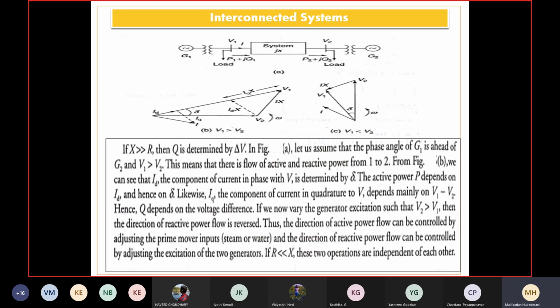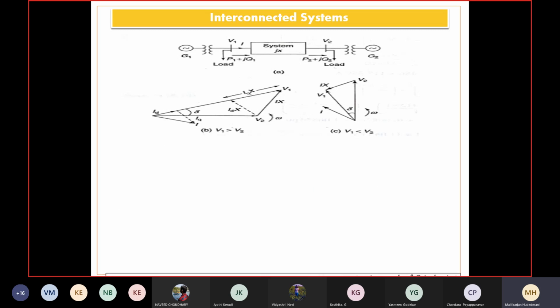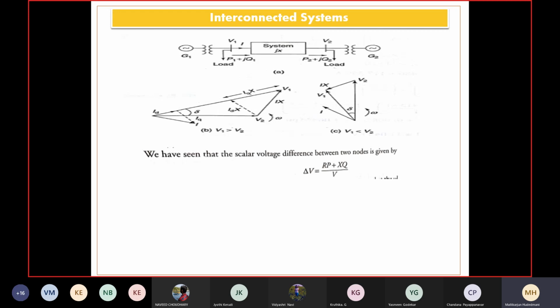Therefore, both the control loops in the generating system are very interesting. They are independent and they are interconnected, such that there should be a P balance and there should be a Q balance side by side. So they have to be systematically organized by the AGC. So, in an interconnected system, a short view of how reactive power flow among them occurs can be seen by a simple block diagram. Then we have seen the scalar voltage difference, a small one more line of paragraph is here.